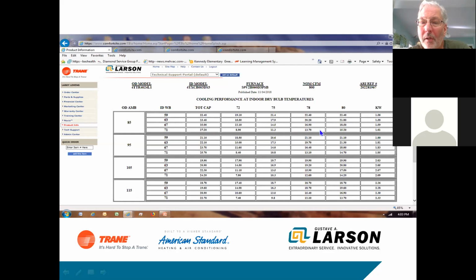So that's all latent load. As the humidity comes down in the space, now my sensible cooling will be up about 22,000, and my latent drops to, well, that's actually total capacity, 22,000. So if you look at it, a 2-ton is not really a 2-ton. There's always that sensible latent split. You're never going to get 24,000 BTUs out of a 2-ton unit for sensible cooling. There's always that couple thousand BTUs that's latent load that you really can't count into the calculation. So if this house was really a 2-ton system, if it was 24,000 BTUs required, you'd be a little bit short on the hot days right here. So always keep that in mind also.